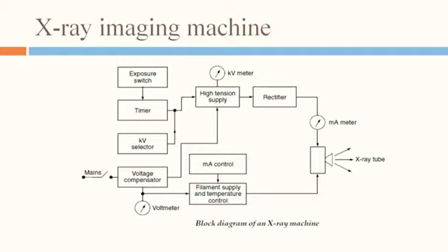The second part of the circuit concerns the control of heating of the X-ray tube filament. The filament is heated with a 6 to 12 volt AC supply at a current of 3 to 5 amperes. The filament temperature determines the tube current, or milliamperes, and therefore the filament temperature control has an attached milliampere selector.